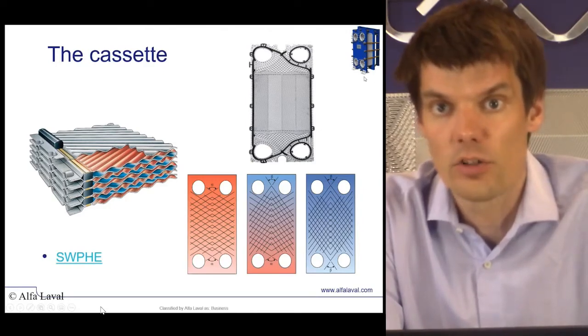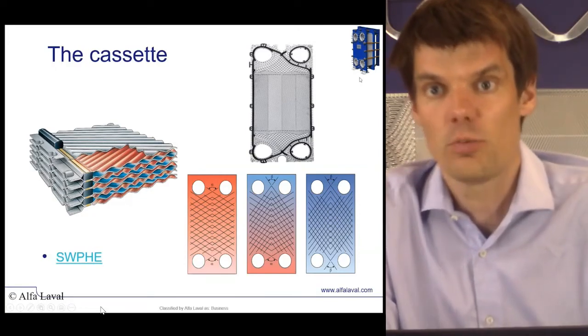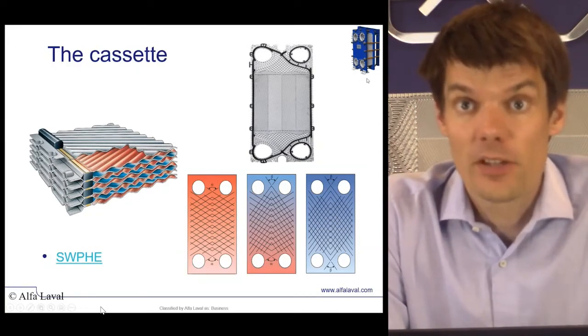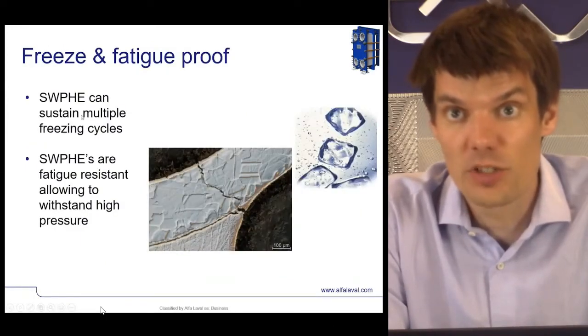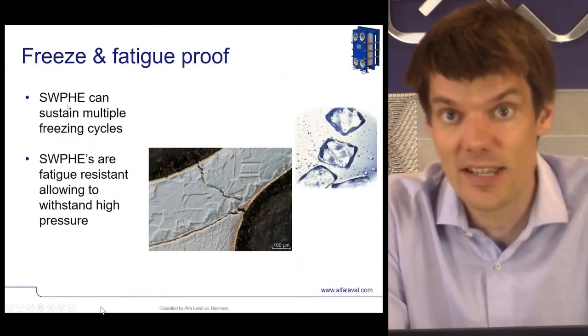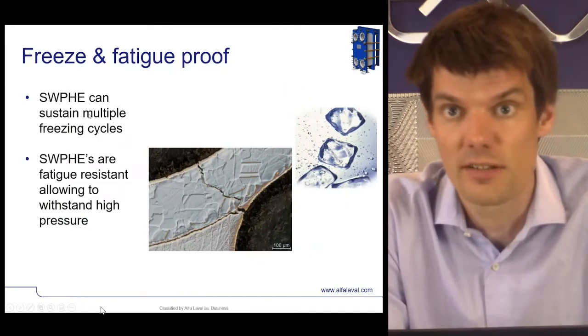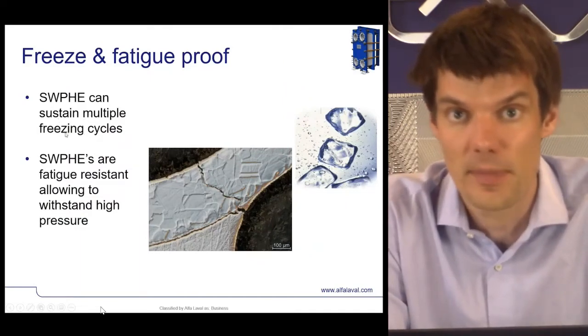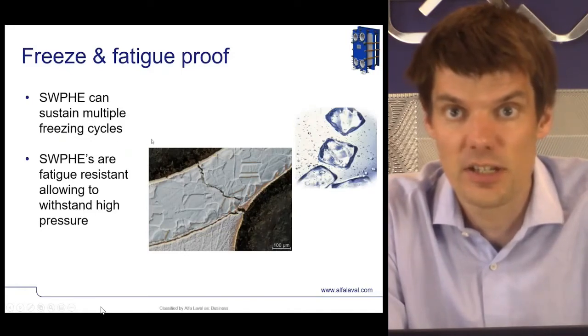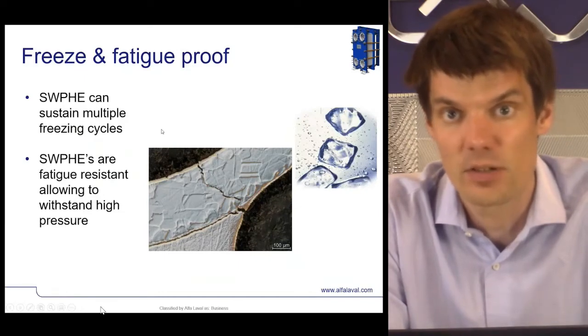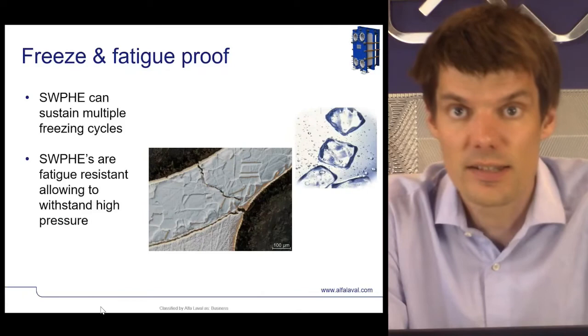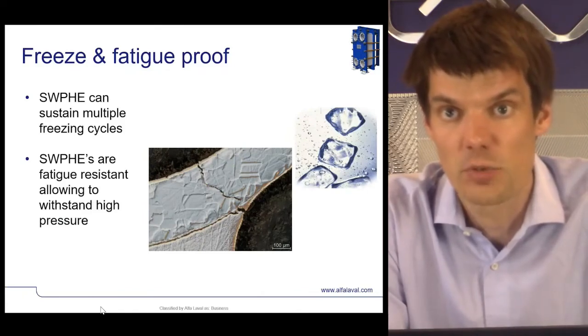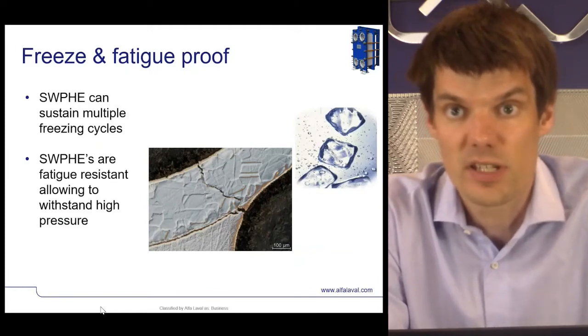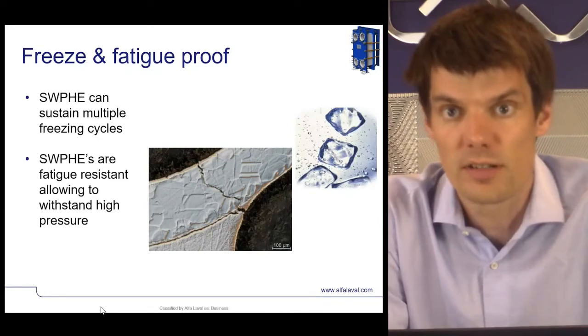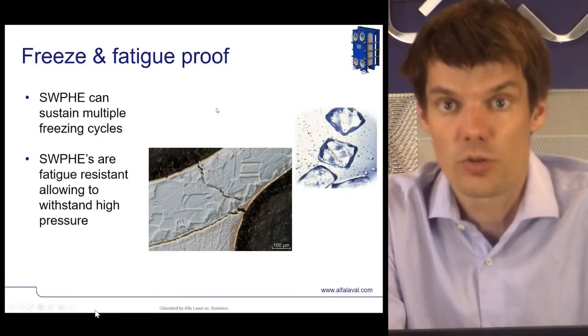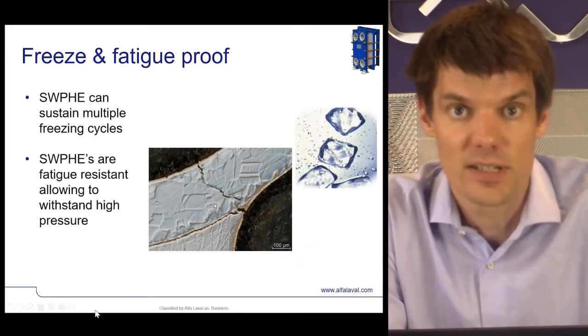However, the design of the semi-welded also brings some additional benefits for the cascade heat exchanger, which we will describe in more detail. One benefit, very convenient in the refrigeration business, where we are operating with low temperatures and want things to stay cool, is that the semi-welded, in opposition to a rigid heat exchanger like a shell and plate or shell and tube, can take freezing without breaking the structure of it. In the case of a semi-welded plate heat exchanger, the difference in volumes will be taken up by the gaskets instead of being transferred to the structural part of the construction. This also makes a semi-welded plate heat exchanger the optimum choice for applications with a high risk of thermal and pressure fatigue. Just like the case with the freezing, fatigue forces will be taken up by the gaskets rather than transferred into the material like plates and cause cracks, which we find here in this picture in the middle of this slide.